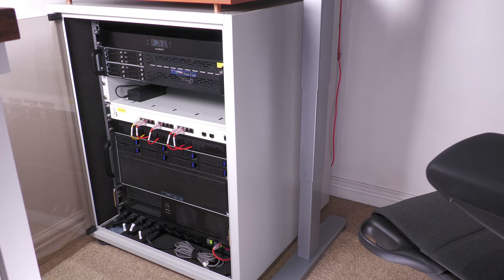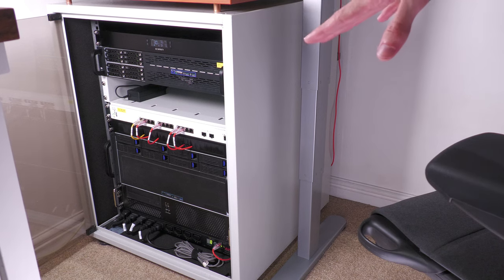I think if I had one complaint, it would be about the controls on the AC Infinity unit. It's only one minor detail, but it would make a huge difference. It doesn't have an ability to set a minimum fan speed. You can set a maximum fan speed, so on smart fan mode, that's the maximum speed it will go up to. However, there is no way to stop it turning the fan completely off if the rack is too cool. The difficulty is that with this rack, there is no chance that without the fan running, it would maintain a cool temperature. It will always get too hot and need the fan.